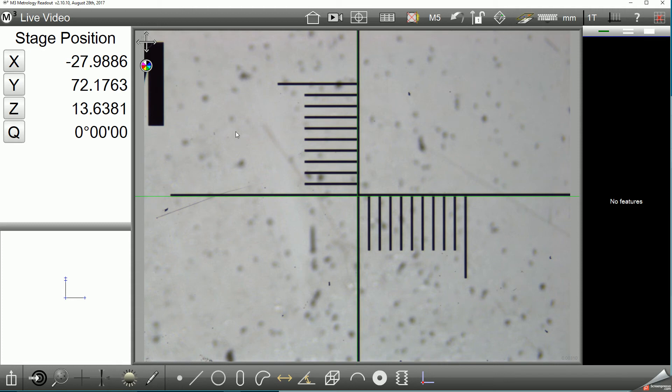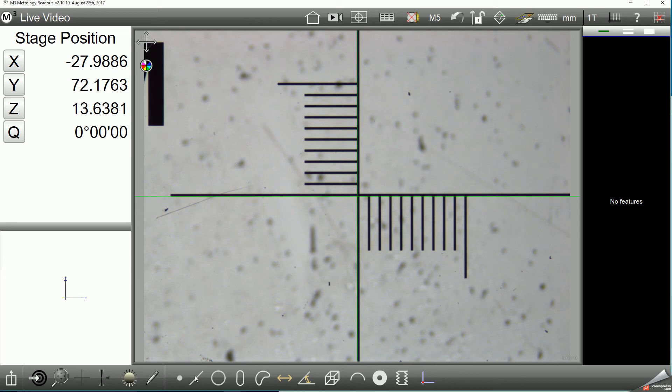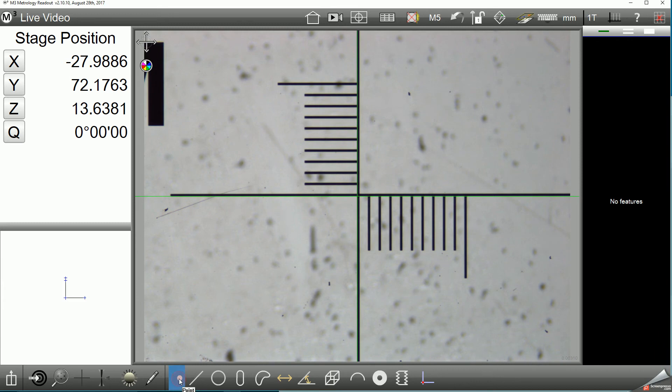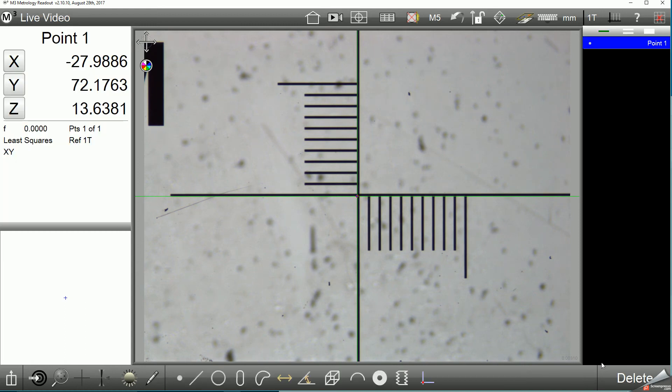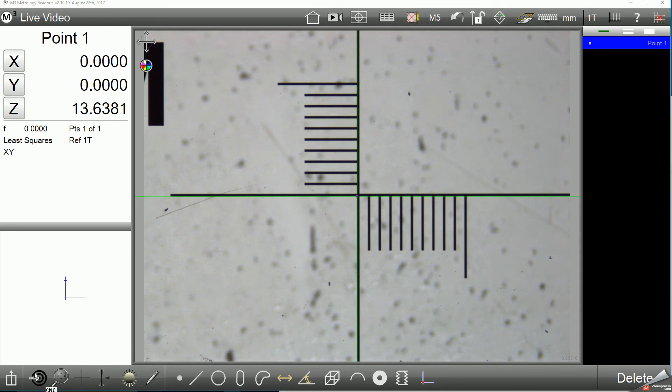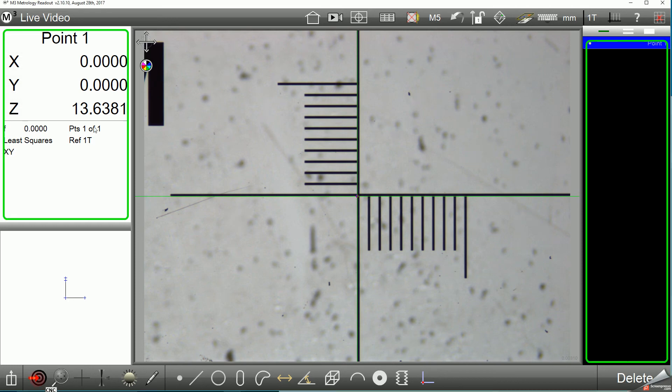The first step in collecting your error correction is to align the calibration artifact with the part coordinate system in the machine to ensure the data that is collected is correct. I'm going to begin by probing a point at the origin position of my artifact. I'm going to zero the X and Y position of that point so I can collect a secondary point to skew my calibration artifact.